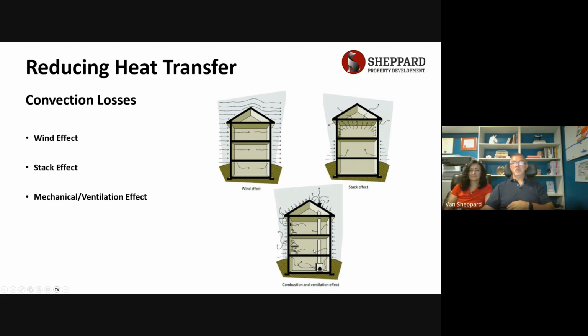Mechanical or ventilation effect. If you have a gas burning appliance in your building, it's going to vent to the outside. It's combustion gases, and that's going to create a low pressure, which is going to encourage air to come in. If you're running the exhaust hood, either the one in the bathroom or the one over your stove, or even if you're running your dryer, all those things create negative pressure, and it's going to pull air into your building. And the only solution to reducing convective losses is to improve your air barrier.